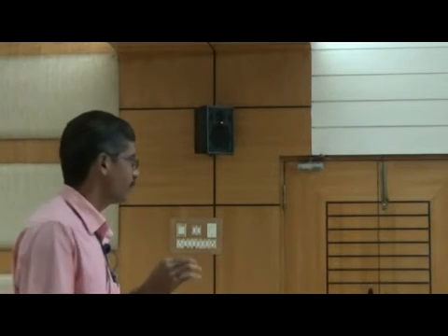I think in your 4th unit you will be studying one of the other problems, unit commitment. From the name itself, you can say what unit commitment is. Suppose you have hundreds of generators. Normally in a practical system, we have a number of generators. So you have to decide which generators are to be turned on during a specific time, because to start or shut down a machine takes a minimum of some 2 to 6 hours. Immediately you cannot shut down or start the machine.